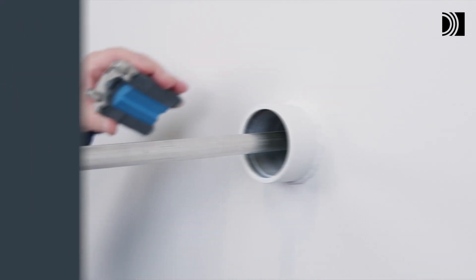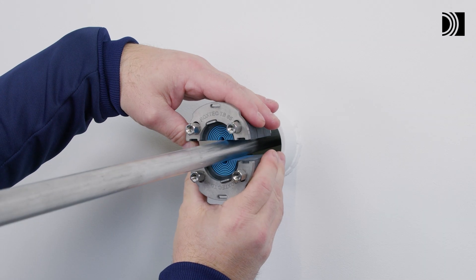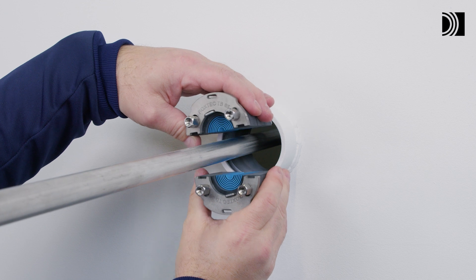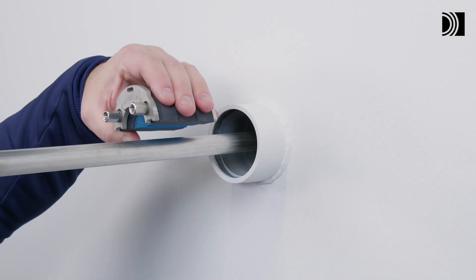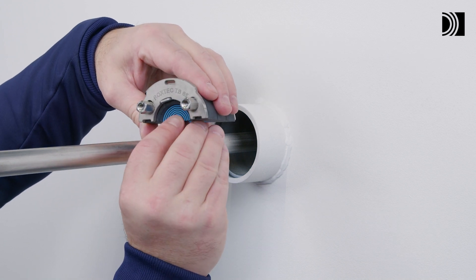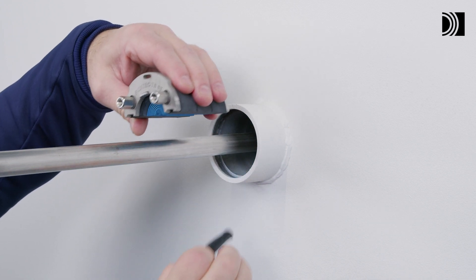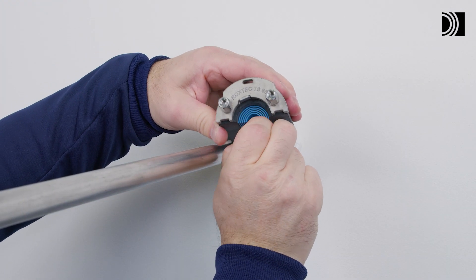Adapt the seal. Achieve a gap of 0.1 to 1 mm. Adapt the seal halves to the cable or pipe size by peeling off layers. The number of layers may not differ by more than one between the corresponding seal halves.